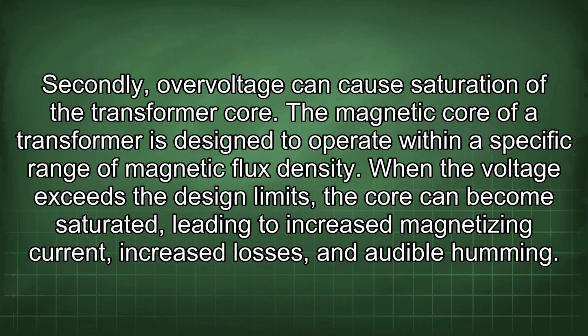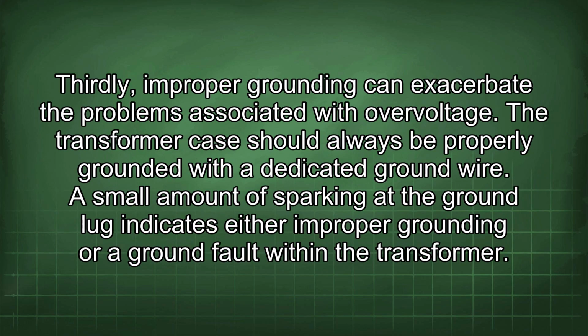The magnetic core of a transformer is designed to operate within a specific range of magnetic flux density. When the voltage exceeds the design limits, the core can become saturated, leading to increased magnetizing current, increased losses, and audible humming. Thirdly, improper grounding can exacerbate the problems associated with overvoltage. The transformer case should always be properly grounded with a dedicated ground wire. A small amount of sparking at the ground lug indicates either improper grounding or ground fault within the transformer.